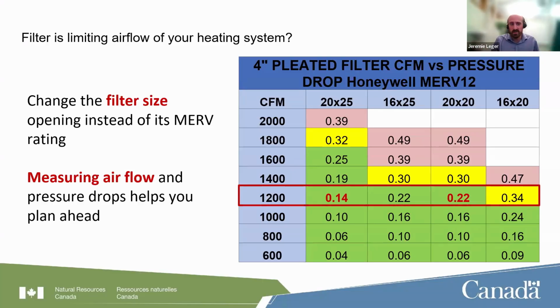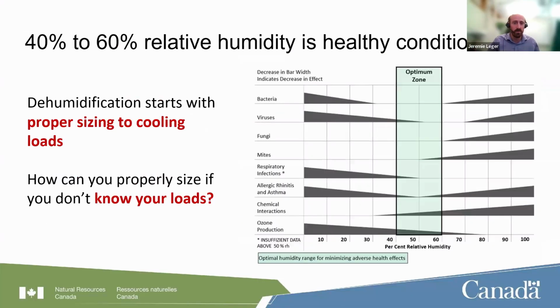How do you know that you're going to run into this type of issue? If you measure the airflow of your existing system, then you can plan for it. I'm going to suggest that measuring the airflow and understanding the pressure drop in your existing ductwork is going to help you make those decisions. Do I need to move to a bigger opening? Will the equipment be able to handle the higher MERV filter? Those are some considerations.